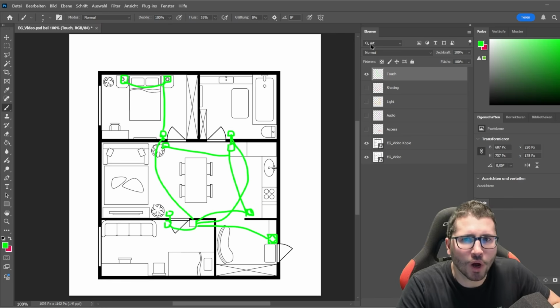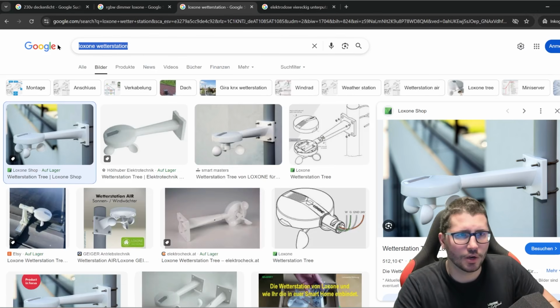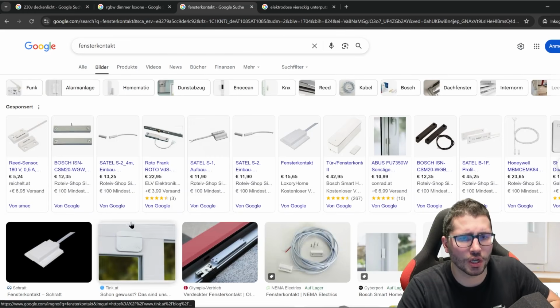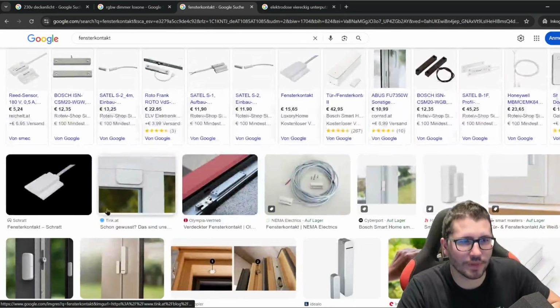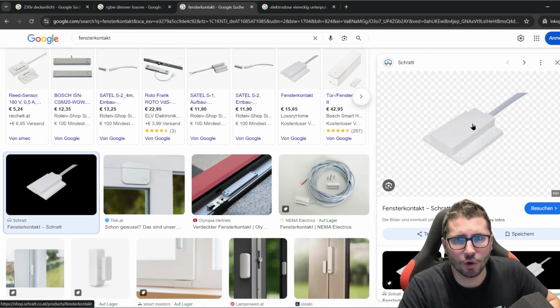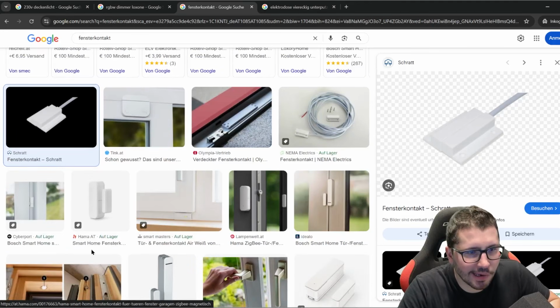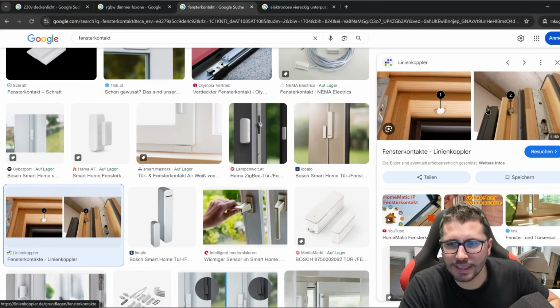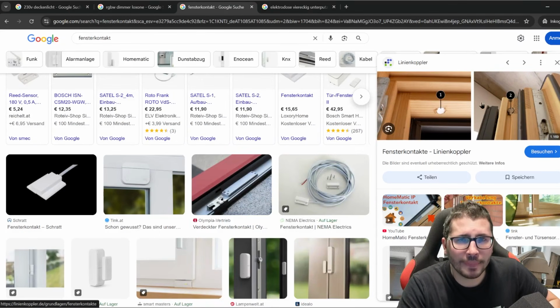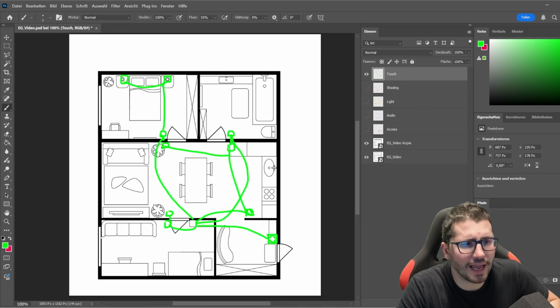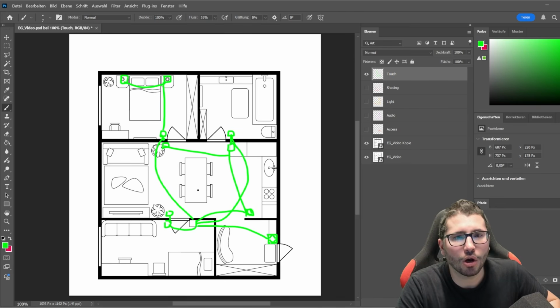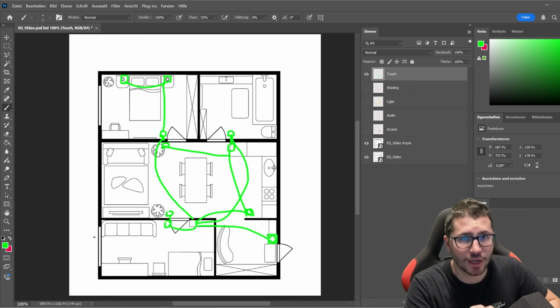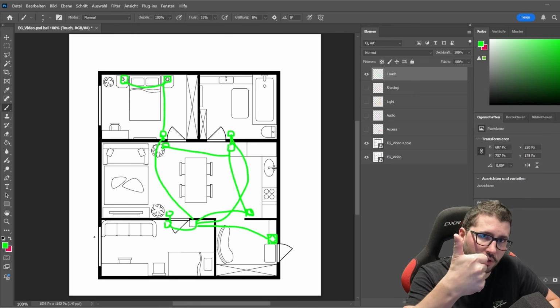And you might have wondered why I did not cover window contacts when we talked about shading. At least in my country, when you buy windows, you can buy them directly with integrated, non-visible window contacts, magnetic contacts, like you see here, magnets inside the window, and then you need to wire them as well somehow. Typically you would need to run every window sensor back to the main DB, or you could say I have one cat cable in a room where I put all of them together, and on one cat cable I can have up to 7 window contacts because I need plus ones and it has 8 cores.